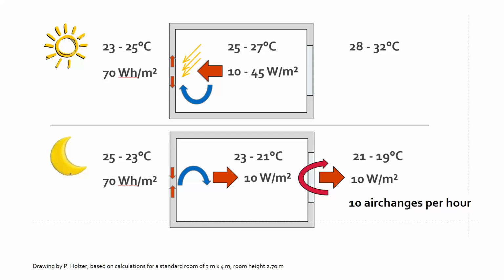And to get the room temperature 2 degrees lower than the wall temperature, we have to rely on an outside ambient temperature that is again roughly 2 degrees lower. And these 3 times 2 degrees are really, from my calculation and observation, quite a robust estimation. Take the outside air temperature during the night and be sure that with a good window design, with a good solar shading design, with a thermal mass exposed to the room's air, you can manage to keep the room temperature 6 degrees higher than the outside temperature. So room temperature minus 6 gives the outside temperature during the night that you need, or the other way around, the outside temperature that you have can secure a room temperature 6 degrees higher.